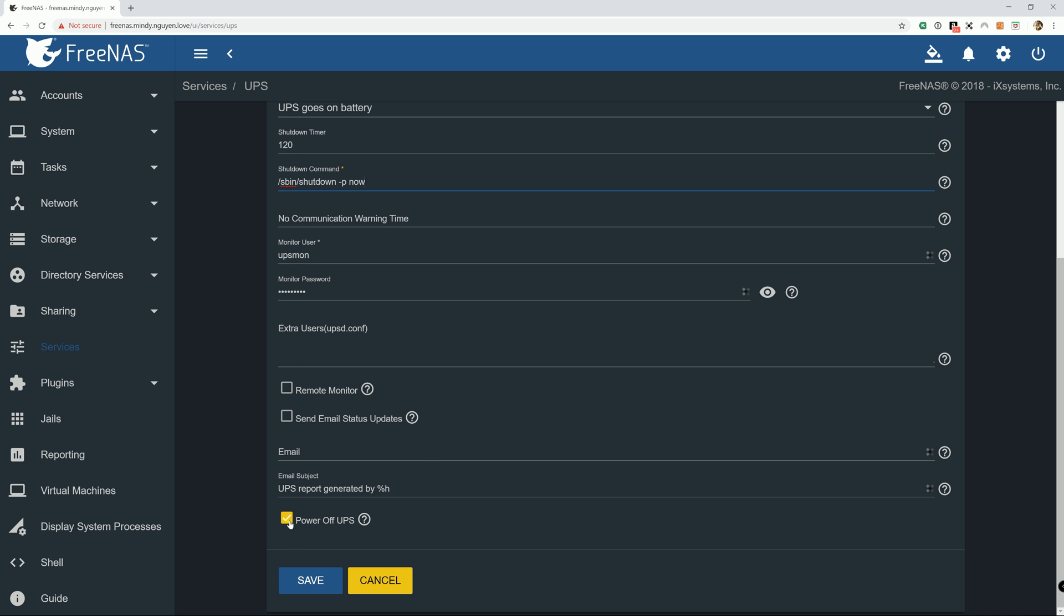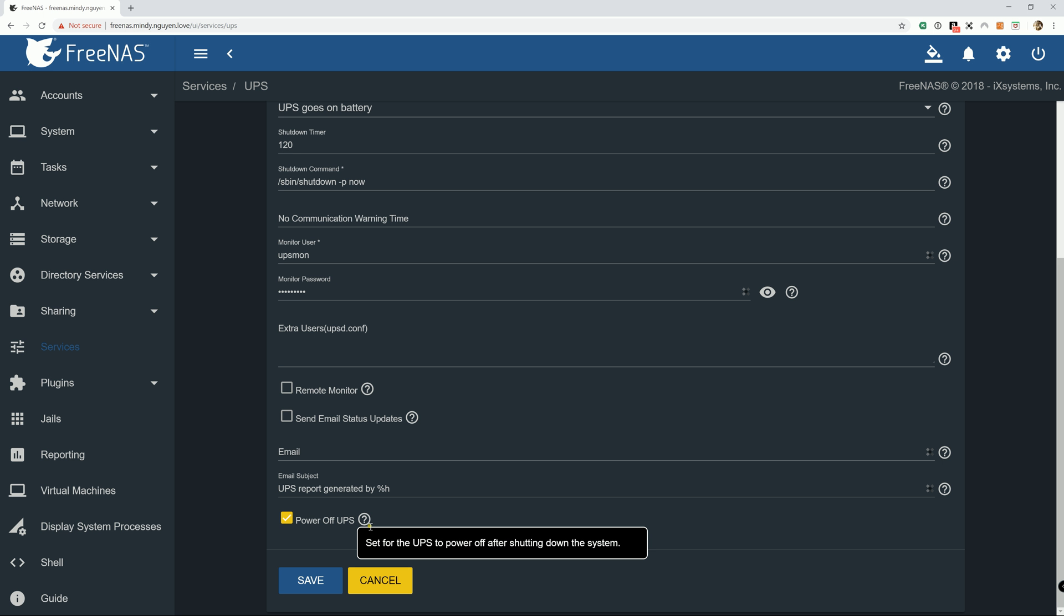Alright, last one. This one by default wasn't checked, but go ahead and check it. Power off the UPS. So why should you power off the UPS? You never know how long the power loss is going to be. So if you keep the UPS running, it might drain out battery eventually. And when it drains out battery and the power comes back on and suddenly loses power again, then you're going to be out of luck because the UPS has no more power to provide for your system.